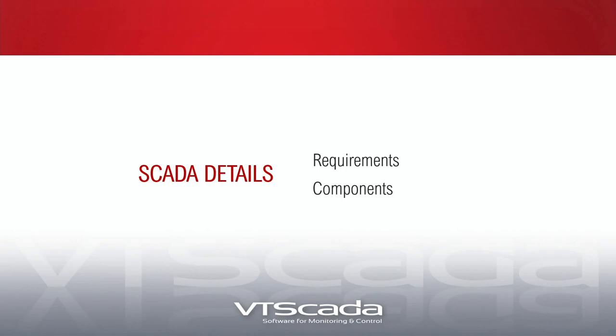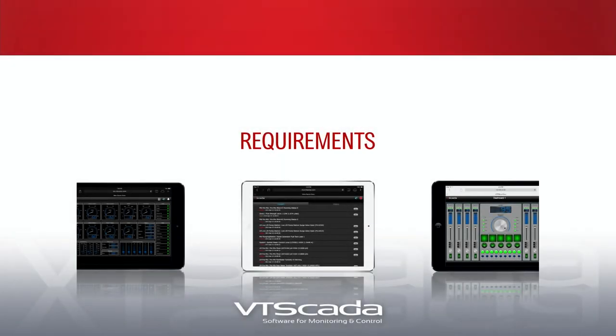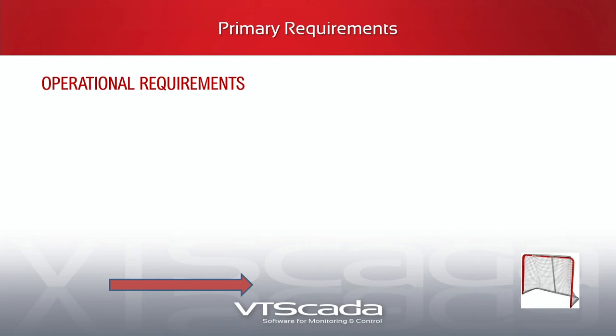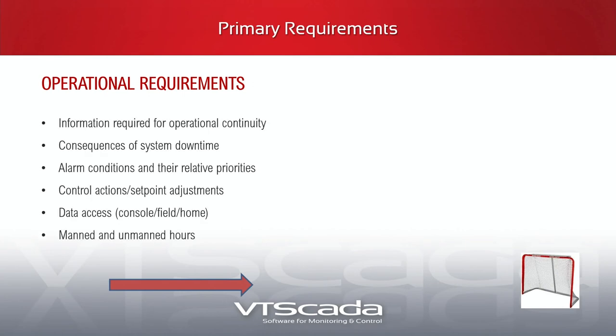We're looking at requirements and then components, starting with requirements. Operationally, we want to make this as functional as possible. We have the information required for operational continuity, and the consequences of system downtime. You want to ensure that if the SCADA software goes down, the system itself can continue operations autonomously. You don't want to rely on any one piece and have a system without fault tolerance. Alarm conditions are a big one.